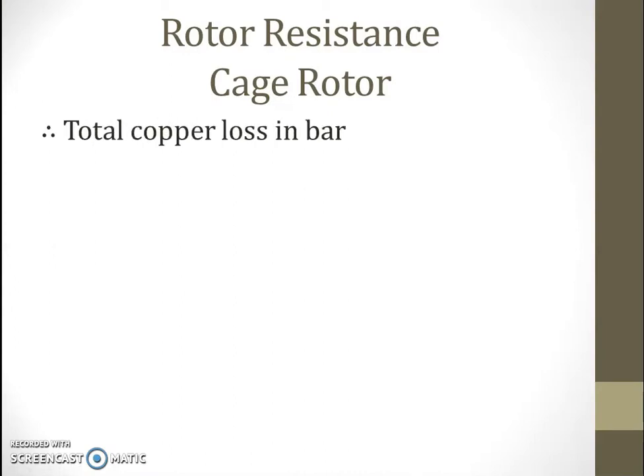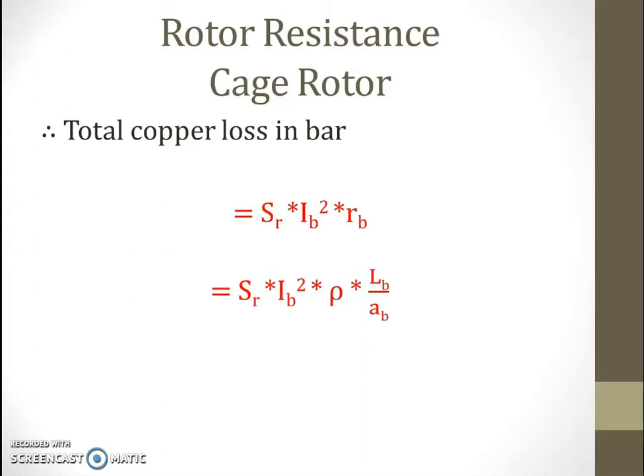So total copper loss in the bar: we have calculated the resistance of each individual bar, and now we calculate total copper loss that is I-squared-R losses. That is IB squared multiplied by RB — where IB is bar current and RB is bar resistance — multiplied by number of rotor slots. Total number of bars equals total number of rotor slots. Substituting the bar resistance, total copper loss equals SR multiplied by IB squared multiplied by rho multiplied by Lb divided by cross sectional area.